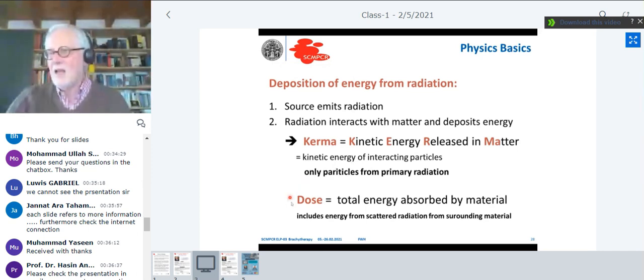If we speak about dose, we include the energy from the scattered radiation. So this is something more realistic - this is what the patient sees. The radiation interacts with a larger area in the patient, and the patient gets dose from the primary radiation and from the side. But in kerma, we don't look at all the scattered radiation - we only look at the radiation coming from the primary radiation out of the source.